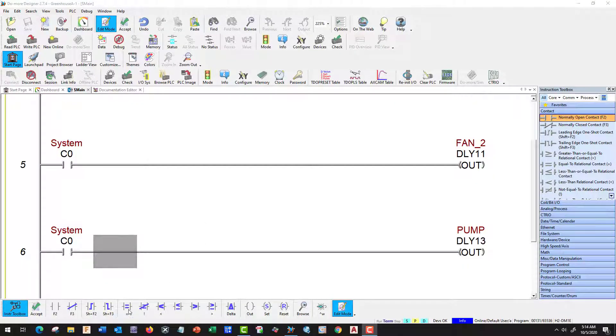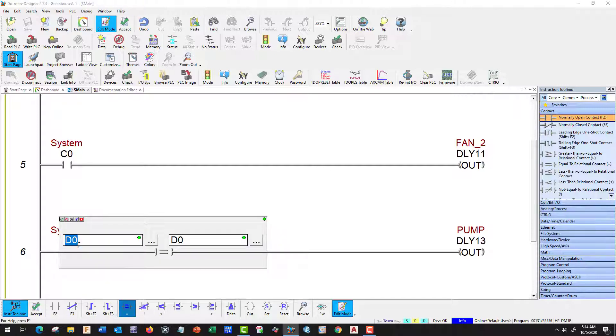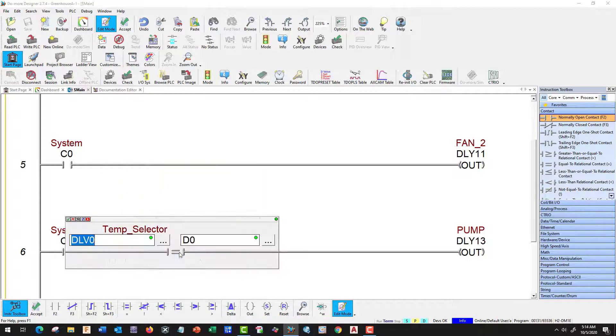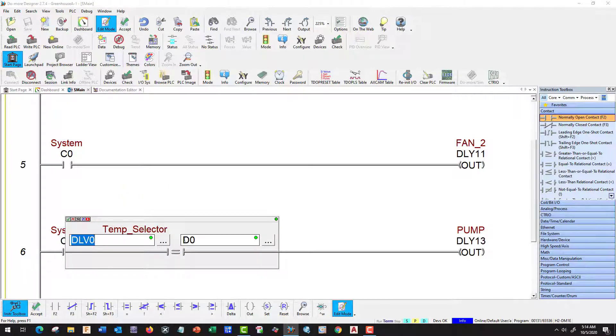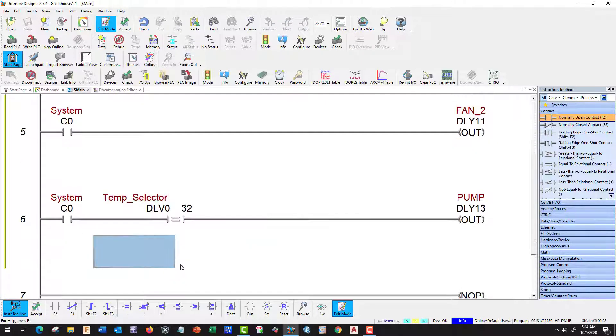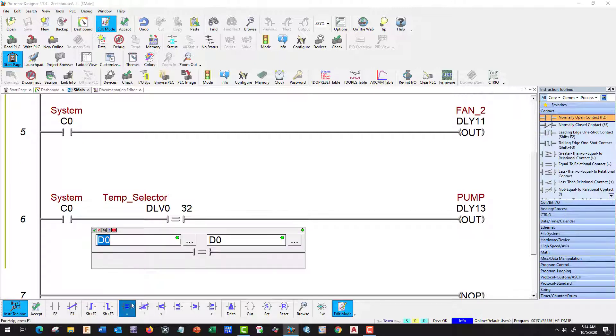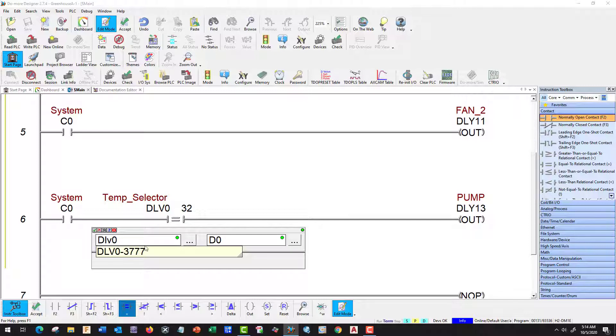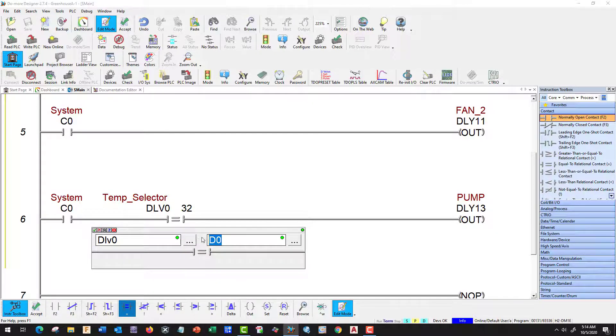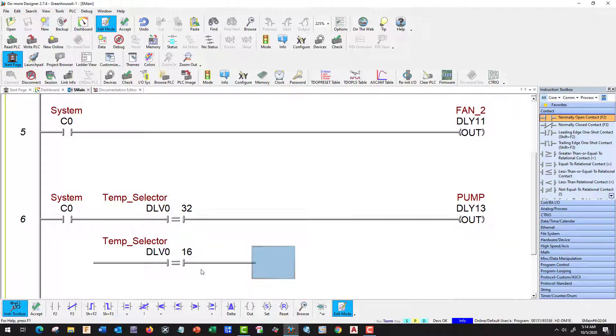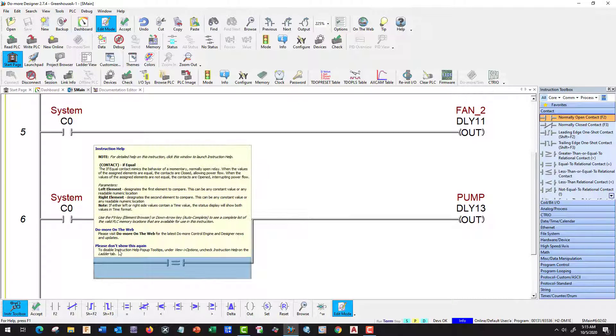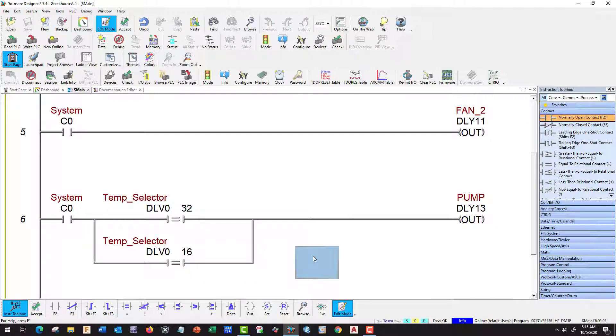Let's start with our pump. It should come on at 90 and 100. So let's use our DLV0, and 100 is going to be 32, binary 32 which is going to match our radio button. Let's add another one here for 90, DLV0, and it's going to be 16. That takes care of our pump.